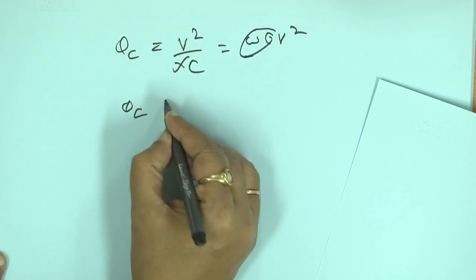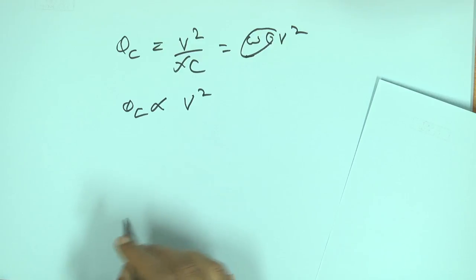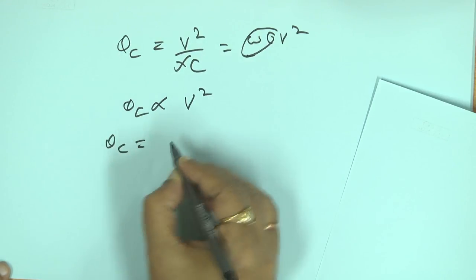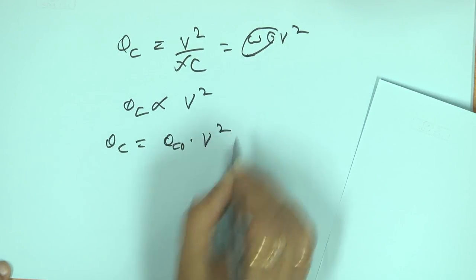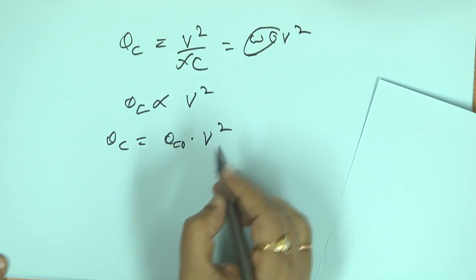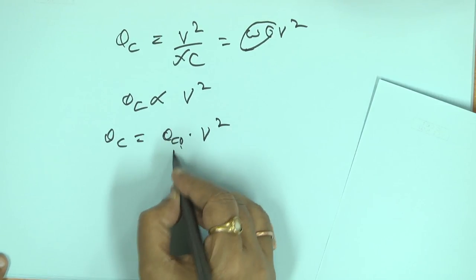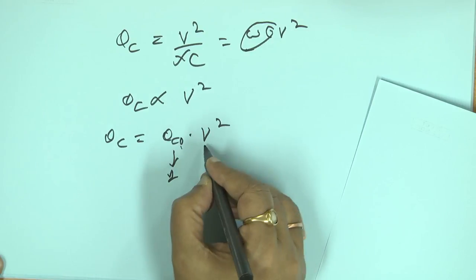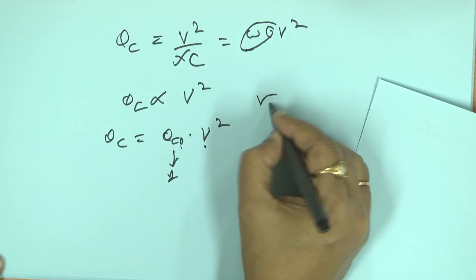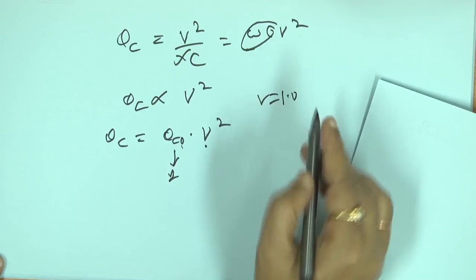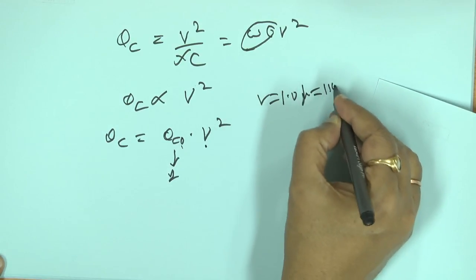That means QC is proportional to V square. So generally QC can be written as QC0 into V square. So suppose QC0 is 1 megavar, and it depends on V in per unit - if voltage V equals 1.0, say it is 11 kV, so 1 per unit equals 11 kV.